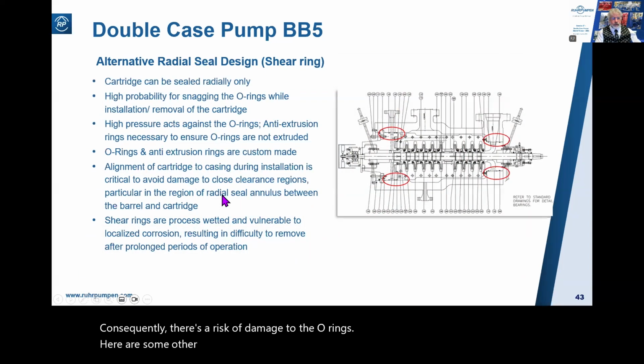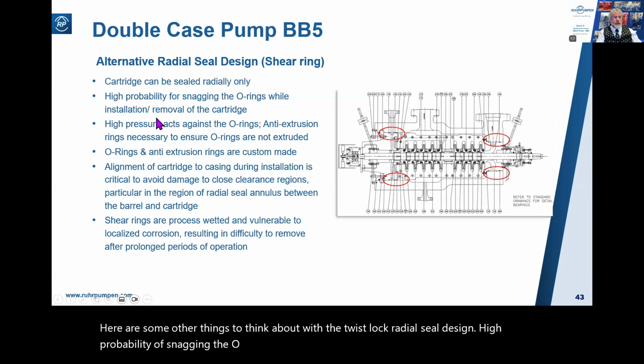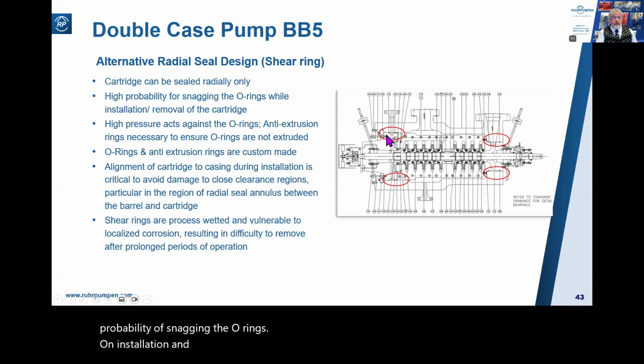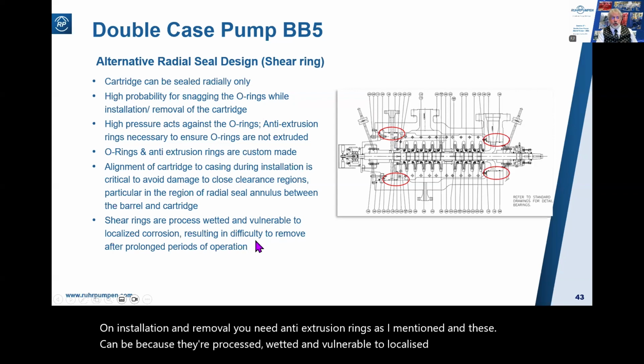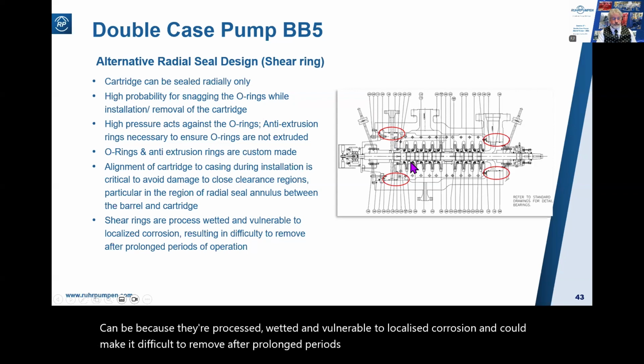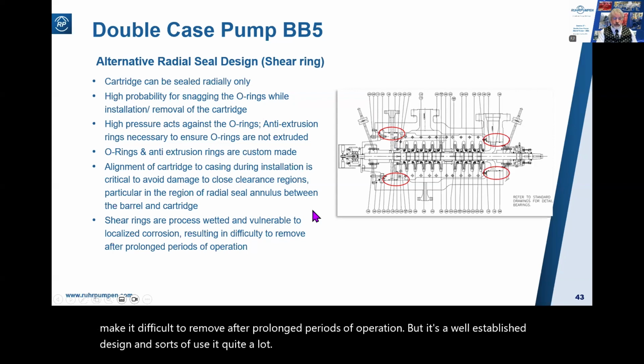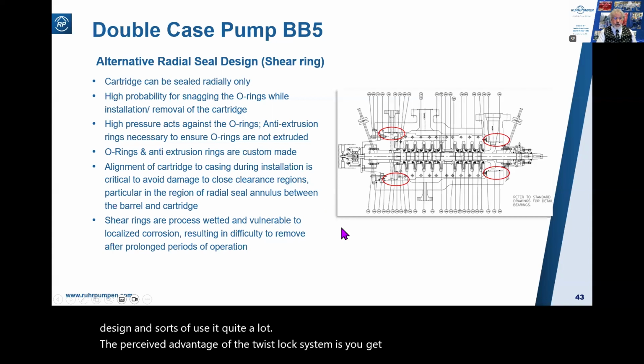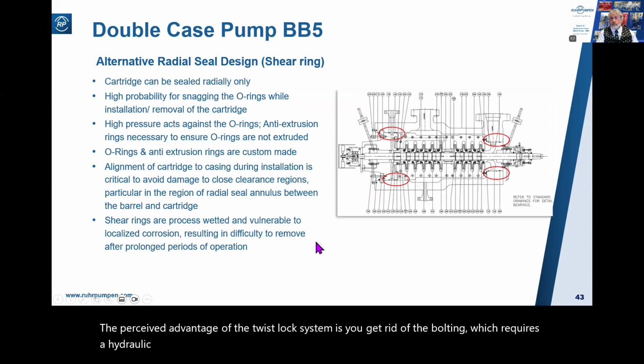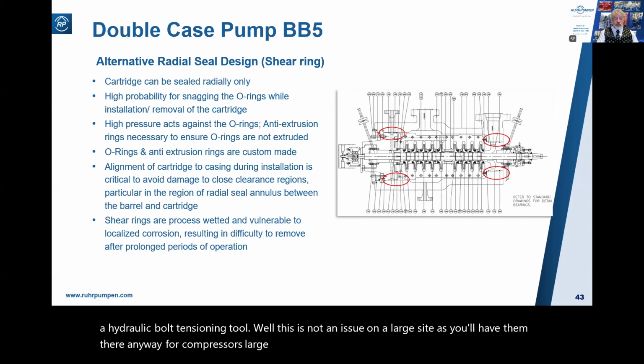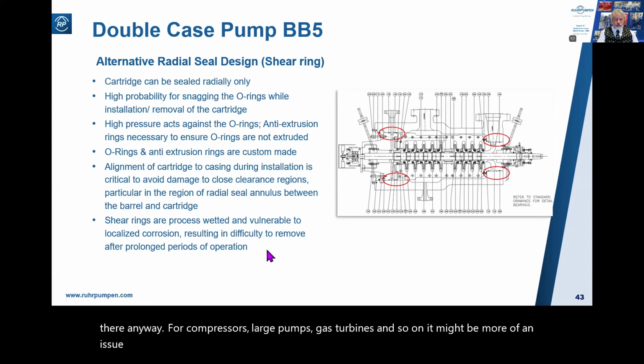Here are some other things to think about with the twist lock radial seal design. High probability of snagging the O-rings on installation and removal. You need anti-extrusion rings, as I mentioned, and these can be vulnerable to localized corrosion because they're process wetted, and could make it difficult to remove after prolonged periods of operation. But it's a well-established design, and Sulzer use it quite a lot. The perceived advantage of the twist lock system is you get rid of the bolting, which requires a hydraulic bolt tensioning tool. Well, this is not an issue on a large site, as you'll have them there anyway for compressors, large pumps, gas turbines, and so on. It might be more of an issue on remote sites.